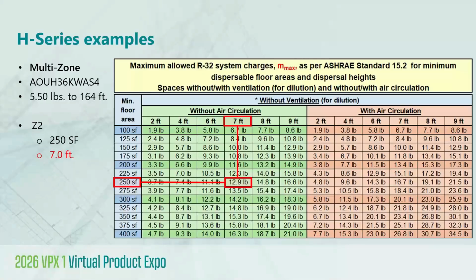So this means that in this case, no mitigation action is required as the refrigerant charge is compliant for that particular space. However, let's assume that in lieu of putting a wall-mounted unit, the customer is committed to using the floor-mounted unit because they are that nice. And in that case, they're relying upon you to find really a creative solution. So this is where practical application comes into play, using the knowledge of everything we just talked about since we started to solve an actual scenario just like this.